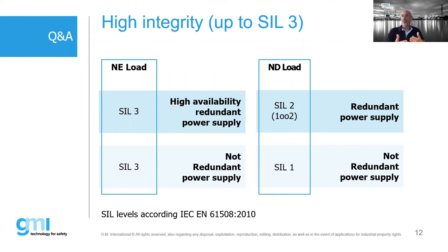Looking at a normally de-energized load with just one power supply, also safe, I can achieve just SIL1. If I want to achieve SIL2, I have to use at least another power supply, and a third if you want to achieve SIL3. That is the configuration that I need for high integrity.